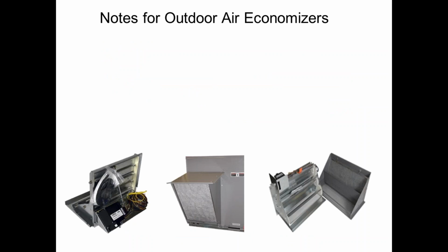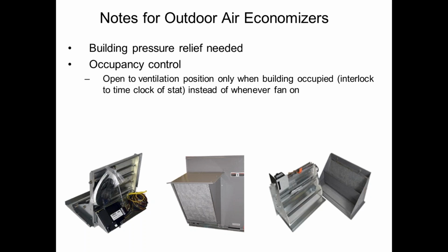All right, a couple other notes on outside air economizers. If I'm going to suck more air into the building, I have to have a way for air to get out of the building. So I have to have a means for relieving the pressure. On small units, this may be a barometric exhaust, right? As pressure builds up in the space, a barometric damper on the return side of the system in the rooftop opens up and relieves that pressure. As systems get bigger, I probably want power exhaust fans to be doing this work for me.